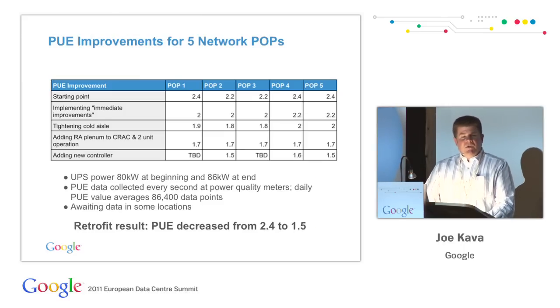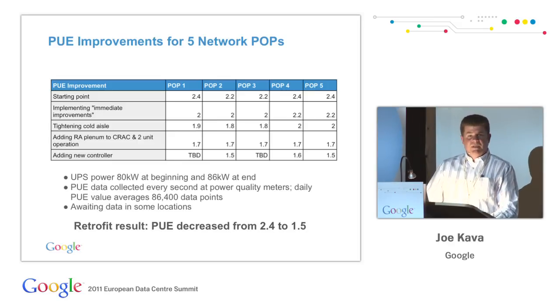We've tabulated the PUE results, and this is across the 5 POPs that we've worked on so far. We're waiting on the final data from 2 of them, but we monitor our PUE real time. We take measurements at our power quality meters every second. Every day, our PUE measurements are an aggregated average of more than 86,000 data points. And we've been monitoring this over a period of several months, and it's remained consistent over that period of time.